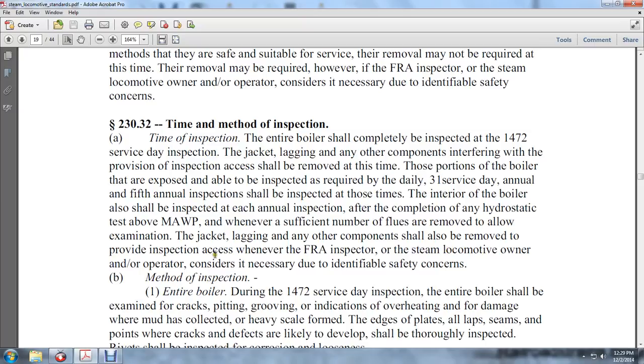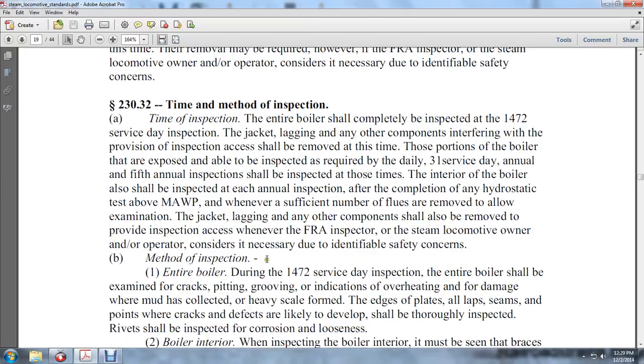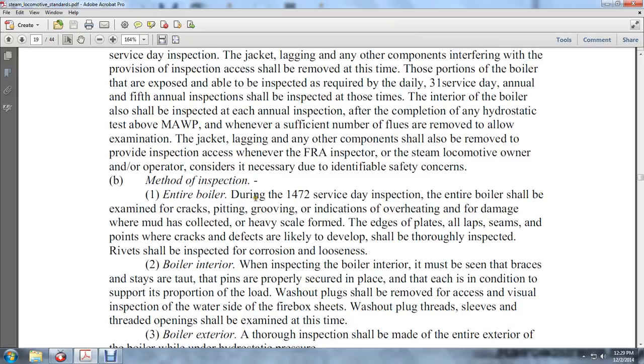The entire boiler, during the 1472 service day inspection, shall be examined for cracks, pitting, grooving, indications of overheating, damage from mud accumulation, and heavy scale formation. All laps, seams, and points where crack defects are likely to develop shall be thoroughly inspected. Rivets shall be inspected for corrosion and looseness. The inspection of the boiler interior must include checking that braces, stays, and taut stays are secure and that pins are properly in place.